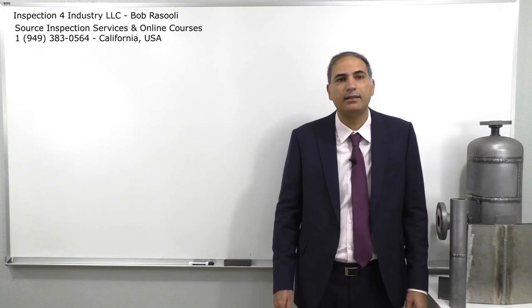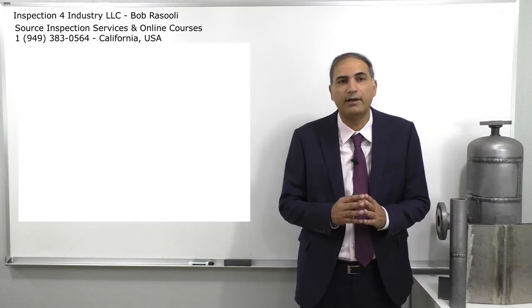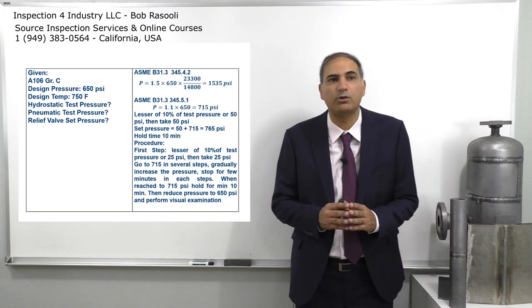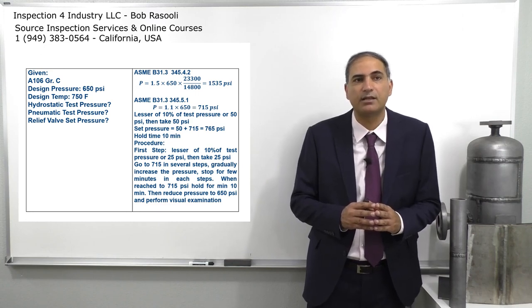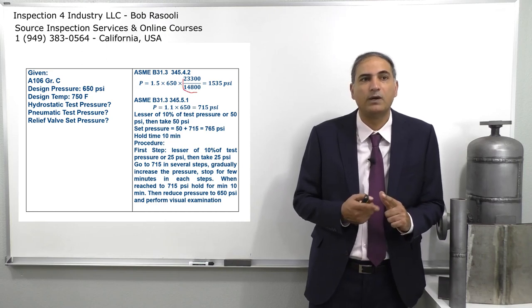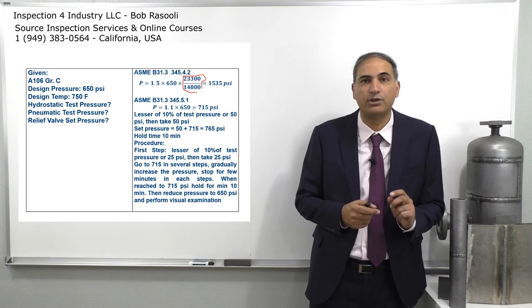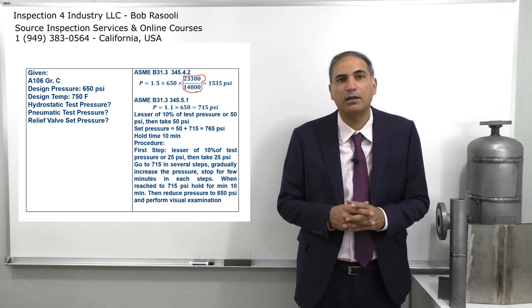Here is an example that you can see on the screen. The material is A106 Grade C. The design pressure is 650 psi and the design temperature is 750 degrees Fahrenheit. We need to find the hydrostatic test pressure, the pneumatic test pressure, and the relief valve set pressure for pneumatic testing. Let's write the formula.